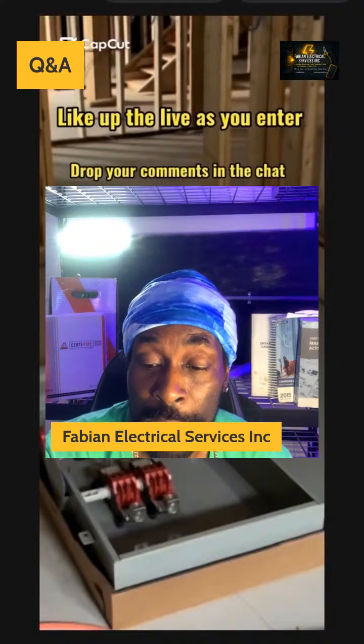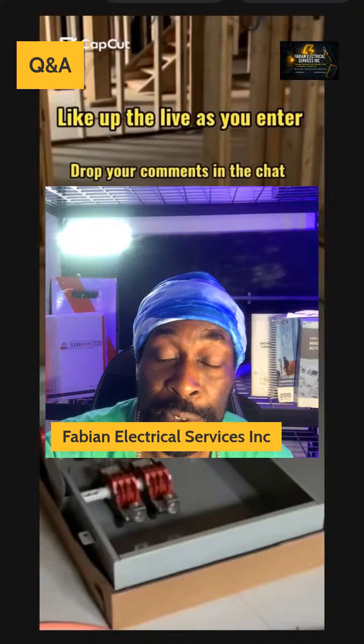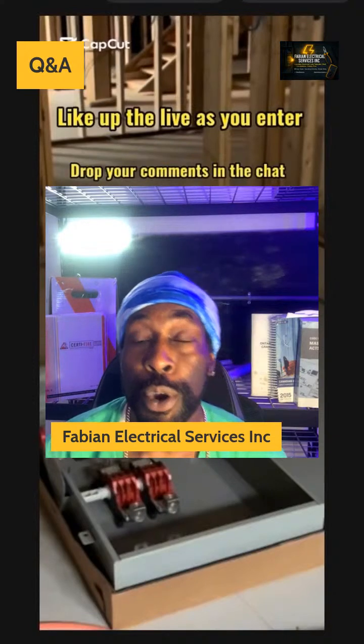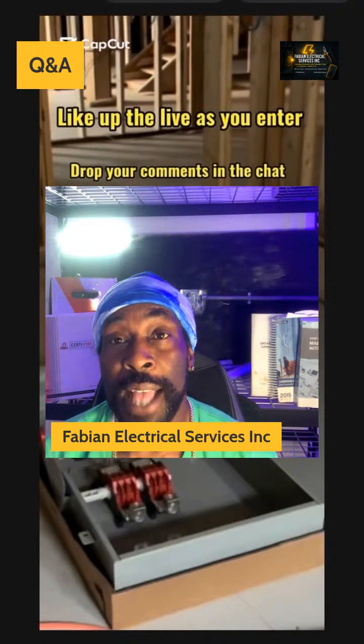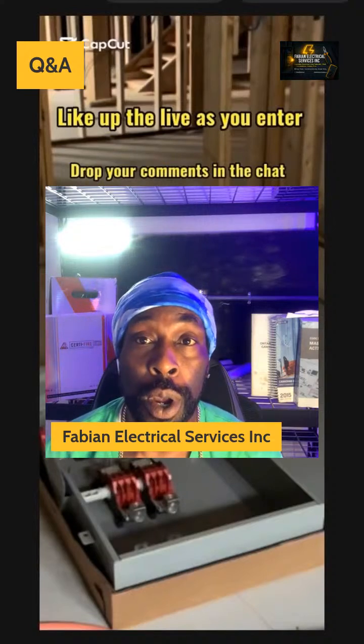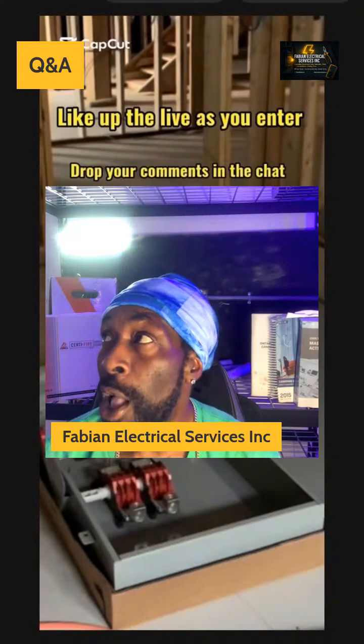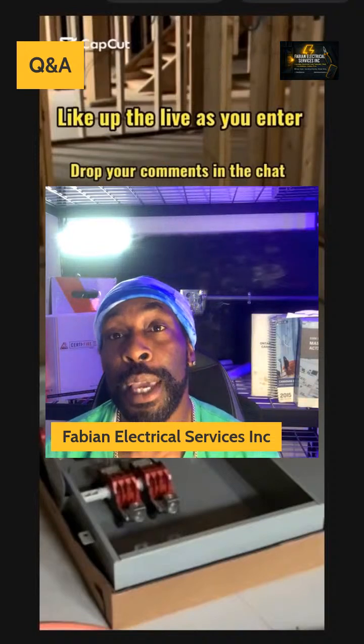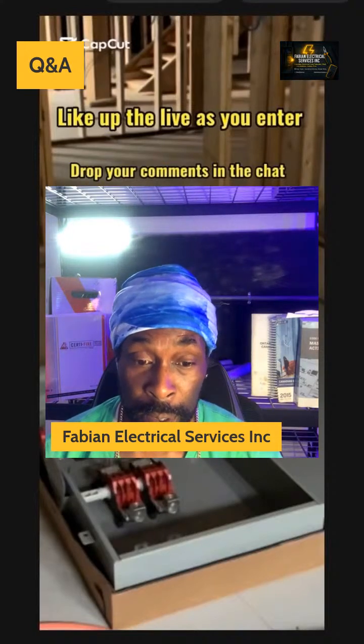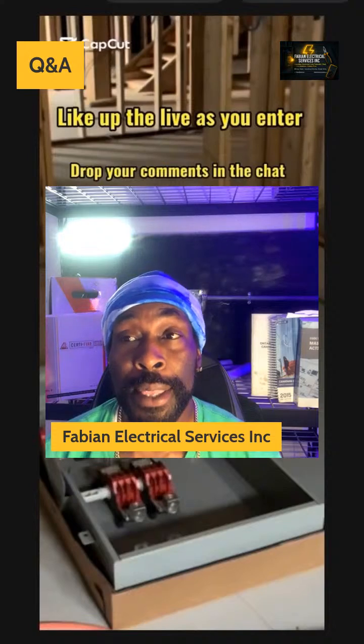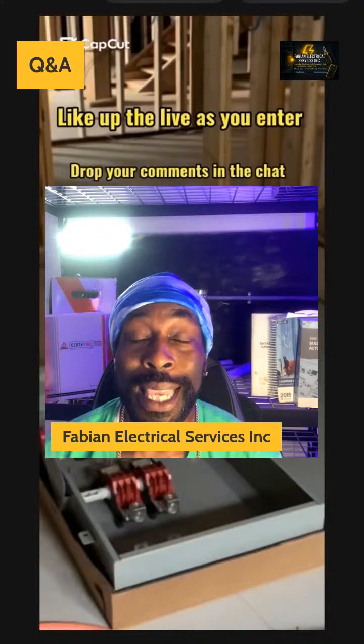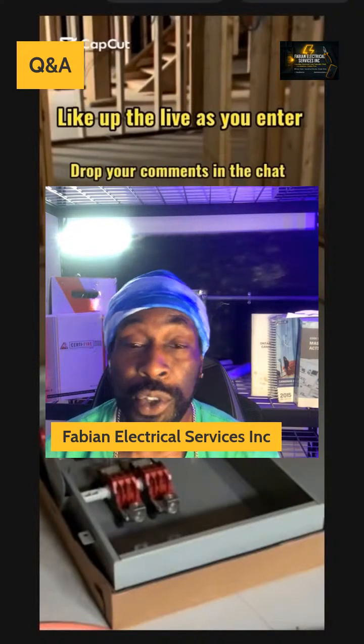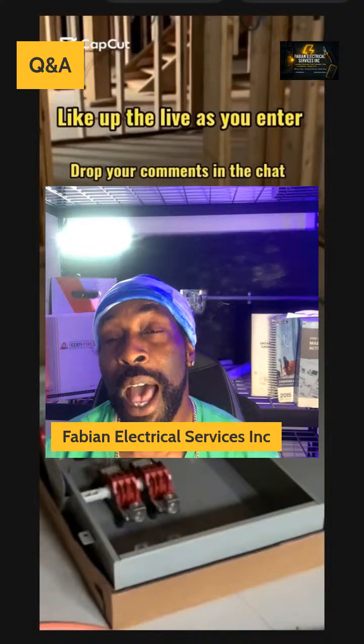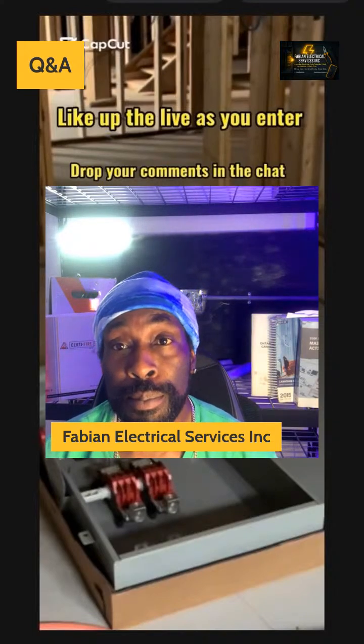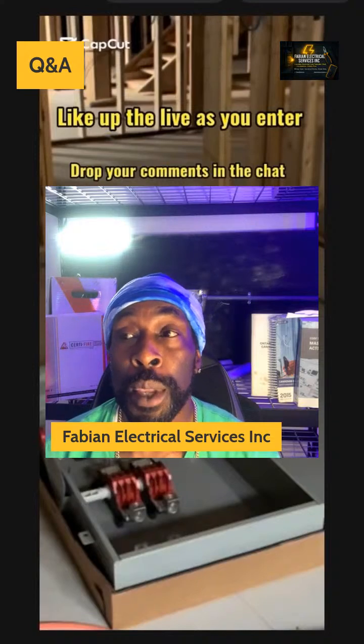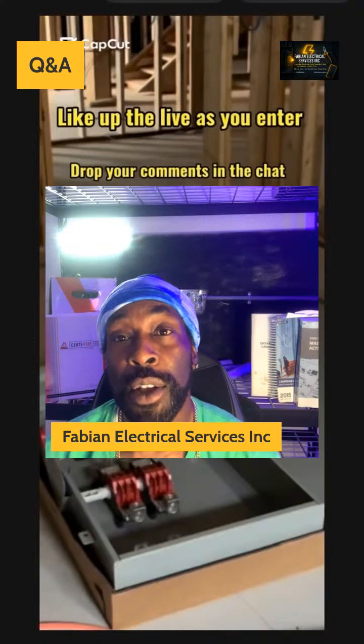So basically what tonight's live stream is about is knowing where to find the correction factor for derating your wires and so on. As we all know, in this dead summer it gets hot, and the wires and so on will heat up. So a lot of times if you undersize your pipe, the pipe has no room for your wires to breathe, which is very important. Your wires need to breathe inside of the conduit.